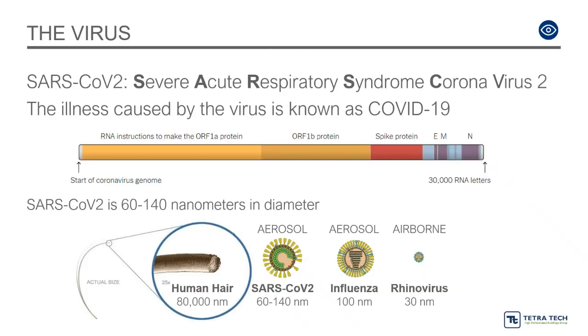I wanted to start with the science of the virus itself. The virus particle is extremely small, 0.06 to 0.14 microns. To put that in perspective, your hair is 80 microns in diameter. It's an extremely small particle, and as such couldn't necessarily be captured even by HEPA filters. But the particles we're concerned about are coagulated with moisture and protein that are infective. They tend to be in the 0.3 micron range, and they can be captured by filtration.